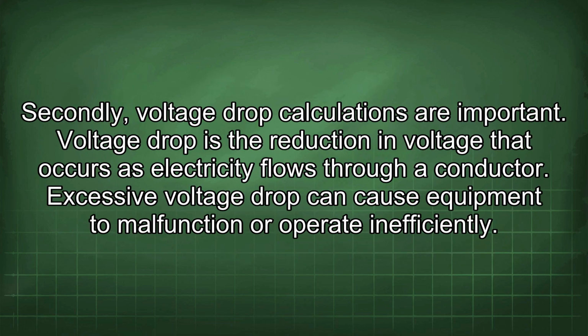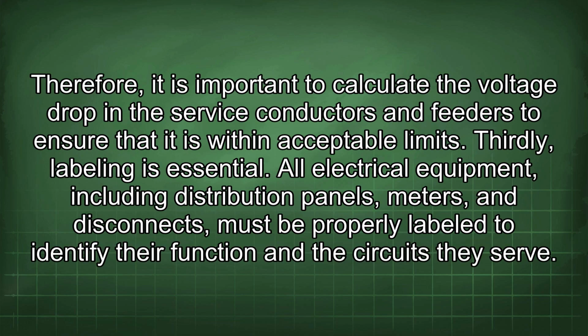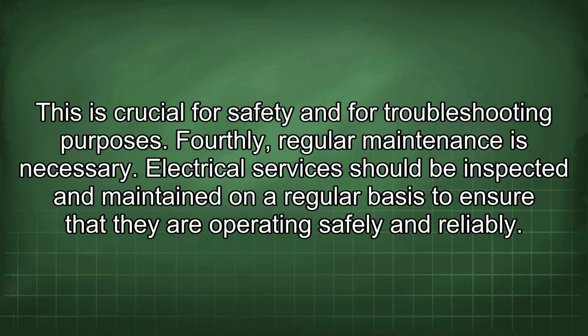Secondly, voltage drop calculations are important. Voltage drop is the reduction in voltage that occurs as electricity flows through a conductor. Excessive voltage drop can cause equipment to malfunction or operate inefficiently. Therefore, it is important to calculate the voltage drop in the service conductors and feeders to ensure that it is within acceptable limits. Thirdly, labeling is essential. All electrical equipment, including distribution panels, meters, and disconnects, must be properly labeled to identify their function and the circuits they serve. This is crucial for safety and for troubleshooting purposes.